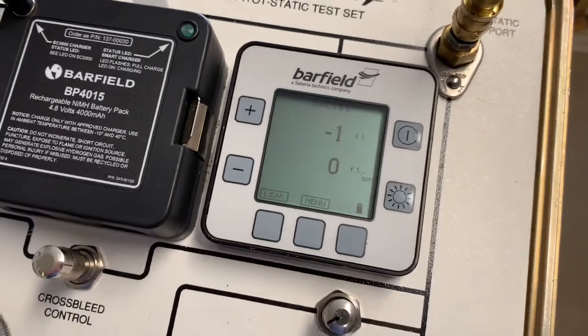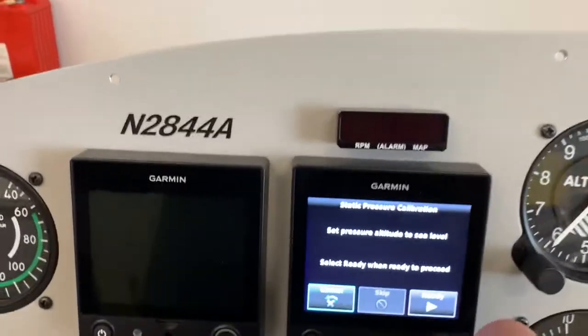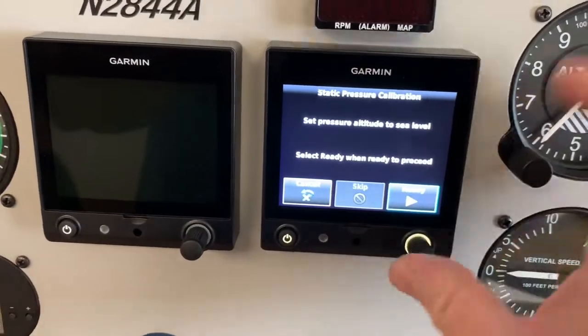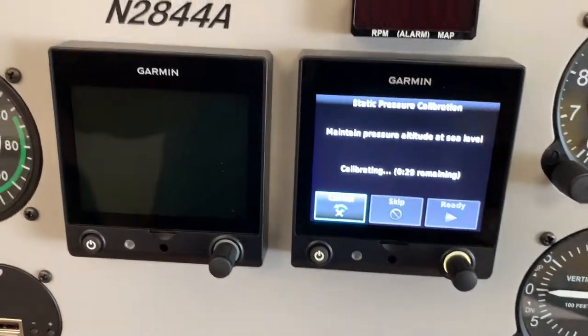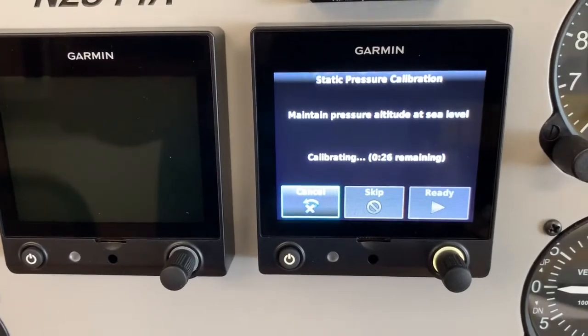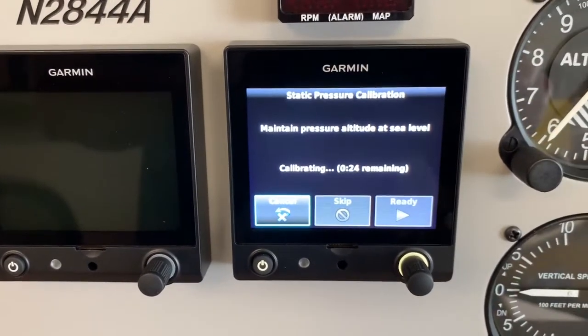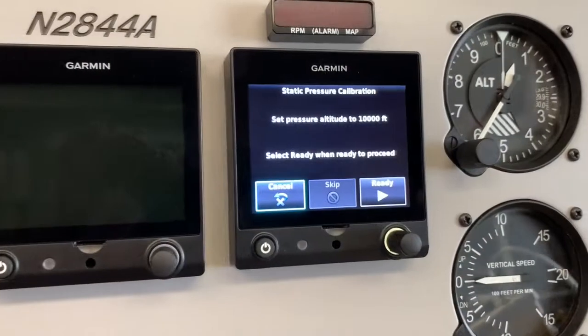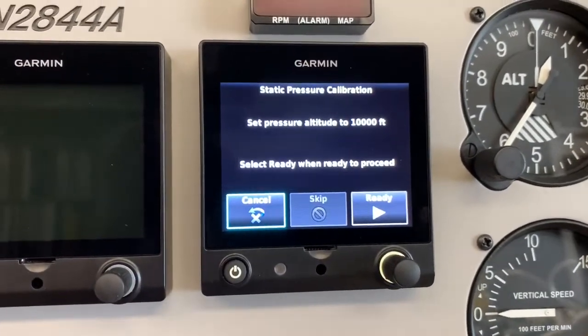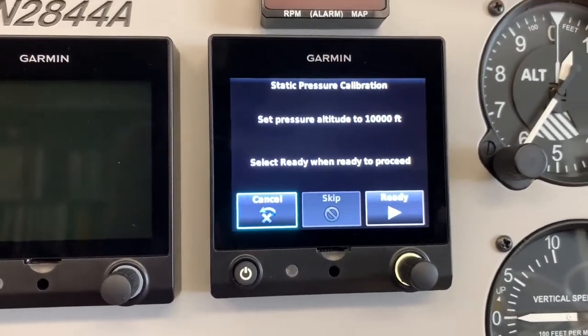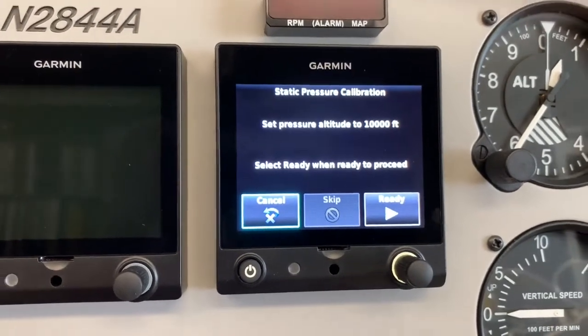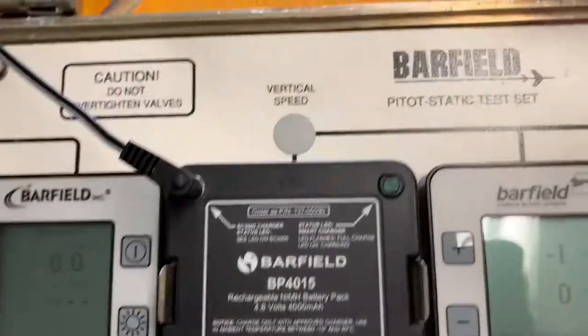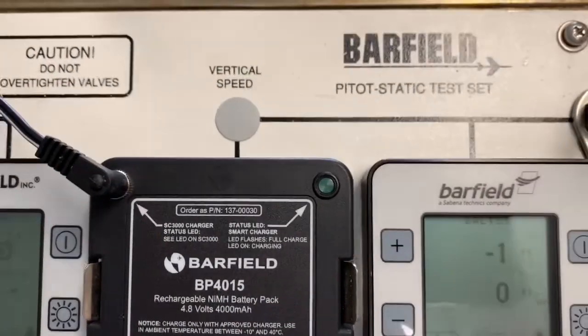All right, we're at a foot. I'm going to call that close enough. So now we dial up over here to ready and we push the button. Okay, and it's going to take 26 seconds. Okay, it has finished its calibration point at sea level, and now it is telling us to go to 10,000 feet. Well, it's going to take me about 5 minutes to get there because I won't go any more than about 2,000 feet per minute climb.